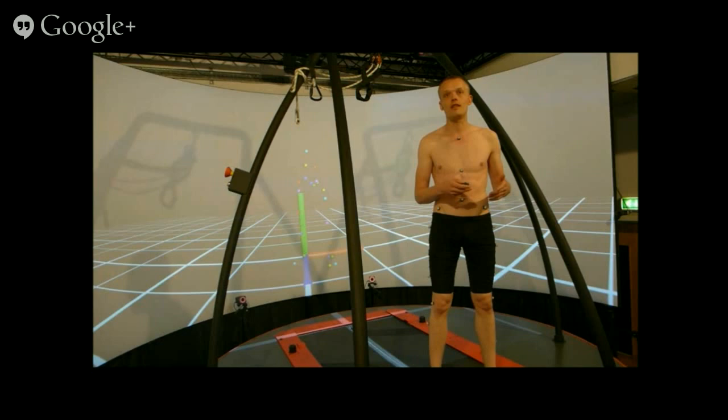However, with this system, when you get on, the treadmill will be stationary, and then as you take a step forwards, the markers will move, the system will start up the belts, and it'll do that individually for each leg. So it feels much more like normal walking. And the motor control of the belts is sufficiently good to speed up and slow down within a gait cycle. So when you walk on it, it doesn't feel like a normal treadmill. It feels much more like normal walking.